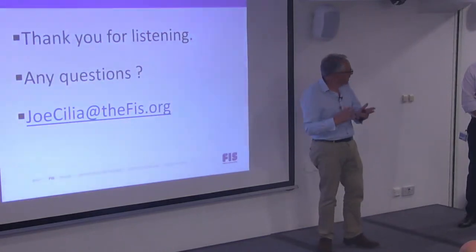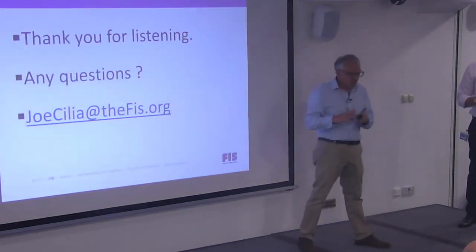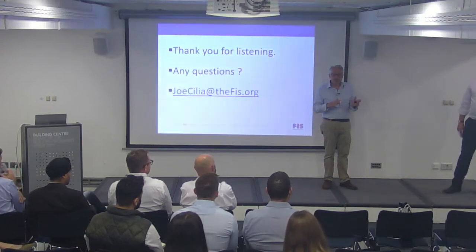There is resistance to fire, its ability to hold back a fire or hold back the heat. But the other is what we call reaction to fire. So reaction to fire, we had a class O, haven't we? Class O, class zero, they called it. There's no such thing. There's no test for class O.